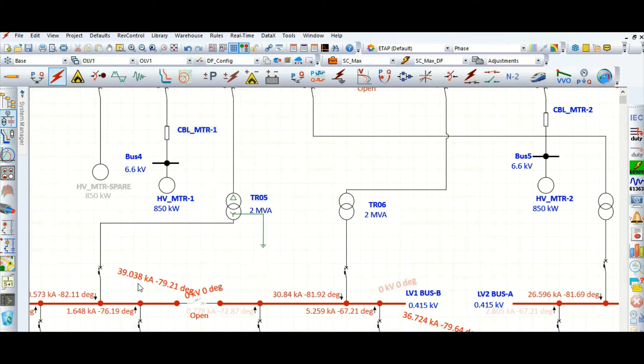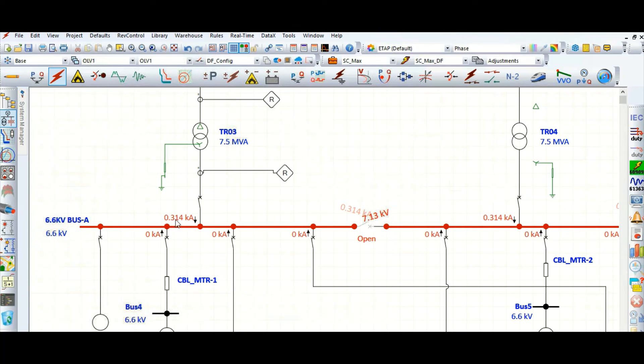Notice that the three-phase short circuit current is less than the single line to ground fault current. This happens because the secondary side star connection is solidly grounded. In contrast, for the 6.6 kV connection through the NGR, the three-phase short circuit current is 4.972 kA, while the single line to ground fault current is limited to only 0.314 kA. This should be kept in mind whenever you are performing short circuit analysis.